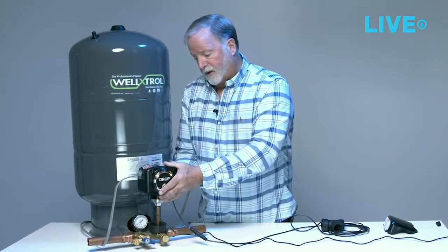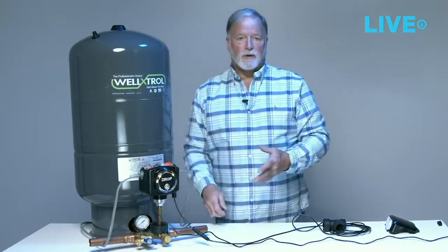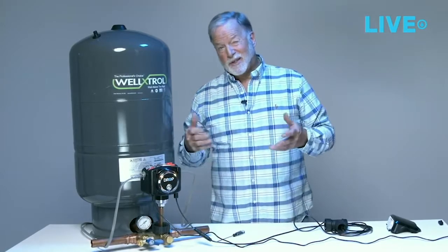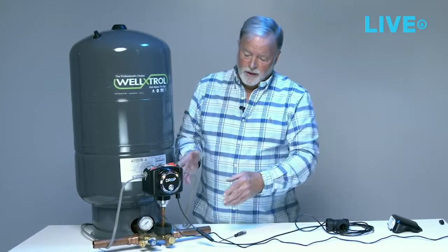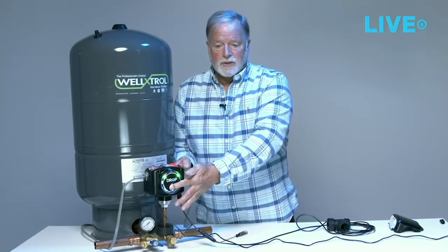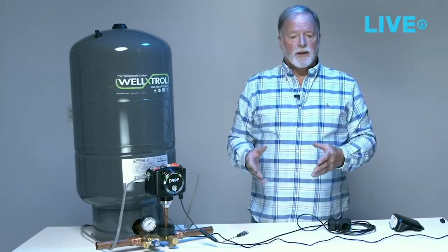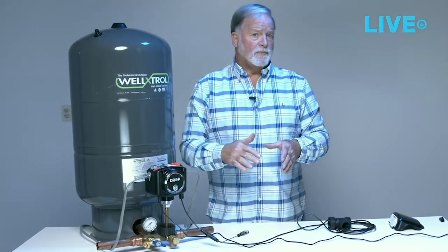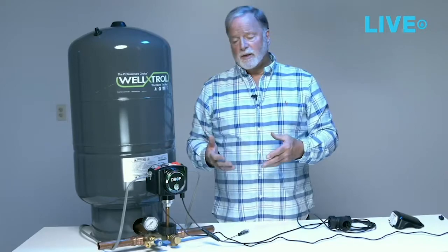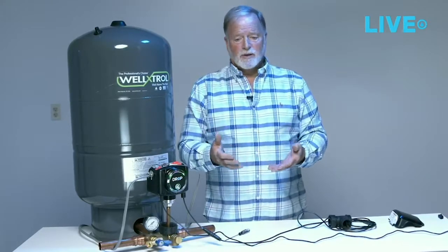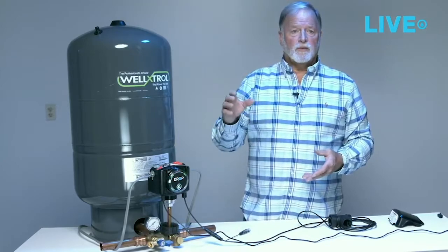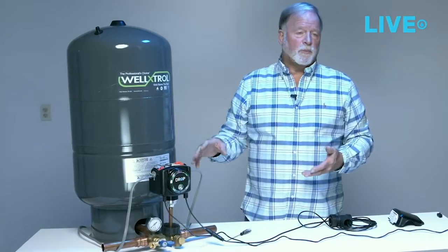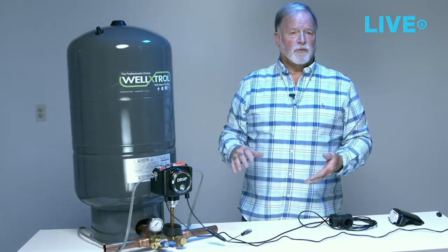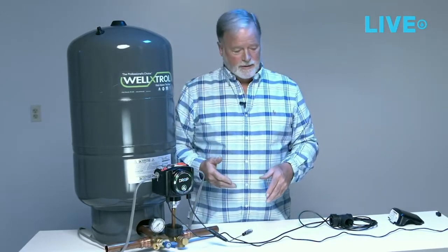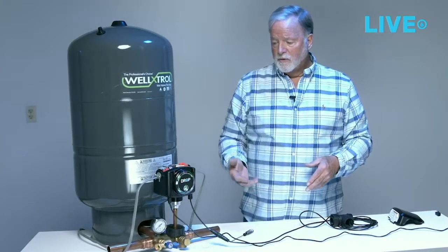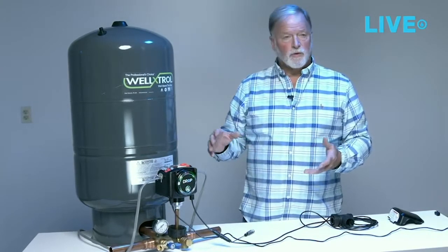So we think that's a big feature. That has a 1,000,000 cycle capability because it's NEMA rated. Actually, it's millions of cycles, as opposed to an electronic switch, where an electronic switch can be troublesome for troubleshooting. It will leak current all the time. The contractor or the installer or the service tech doesn't really know if it's made or not made because you have no visual evidence that the switch is made. So this is really a superior way to do a motor control, as opposed to, I believe, any other similar product out there uses an electronic switch. So the mechanical switch in this is a big serviceable feature.